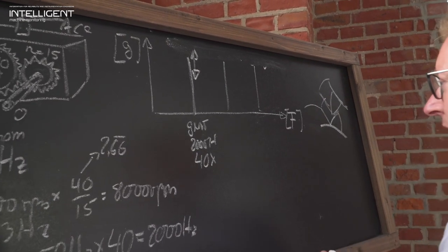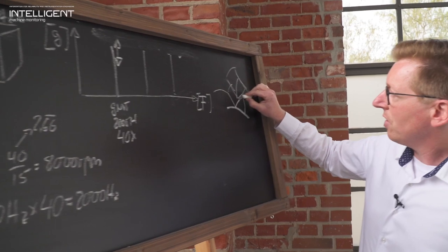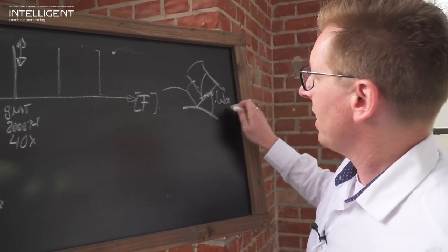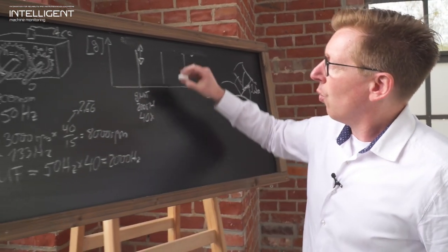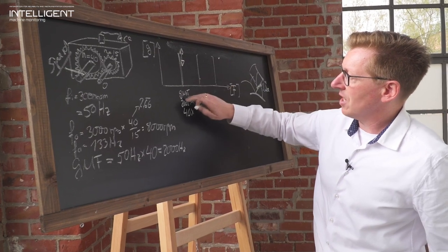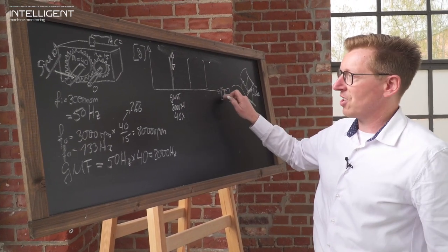in a loading situation load will increase or decrease this peak in amplitude. So load as well as lack of lubrication, having lubrication between these two components is a very key element. Lack of lubrication as well as loading change will be visible in the height of the amplitude of those gear mesh frequency peaks in the spectral data.